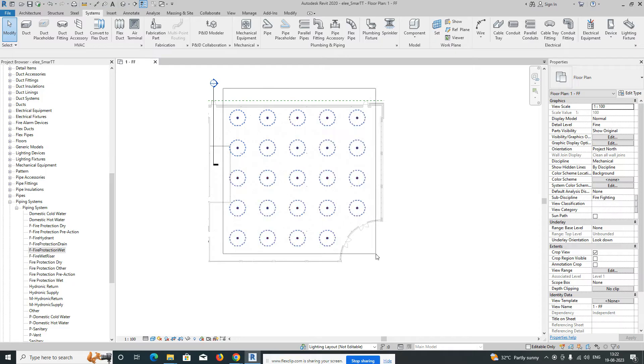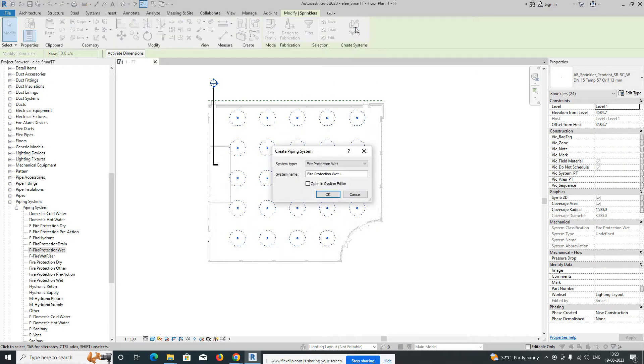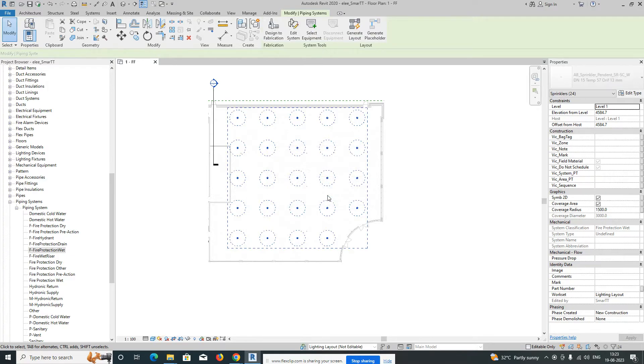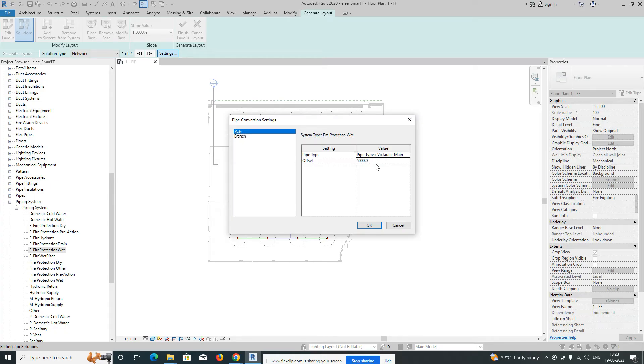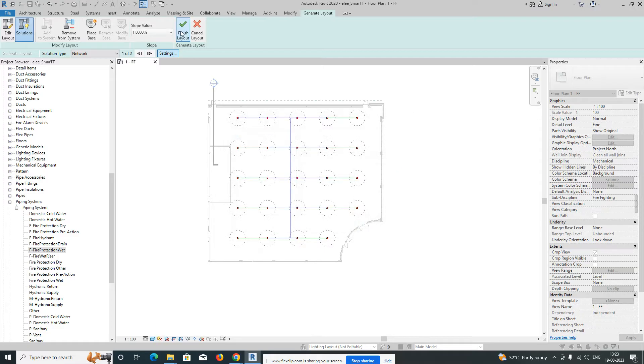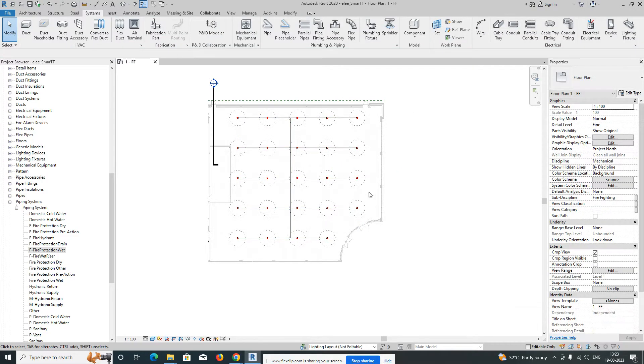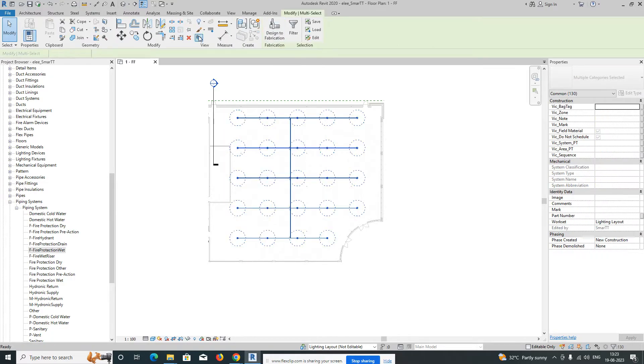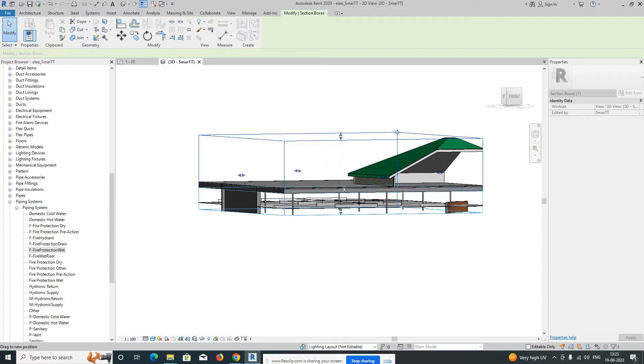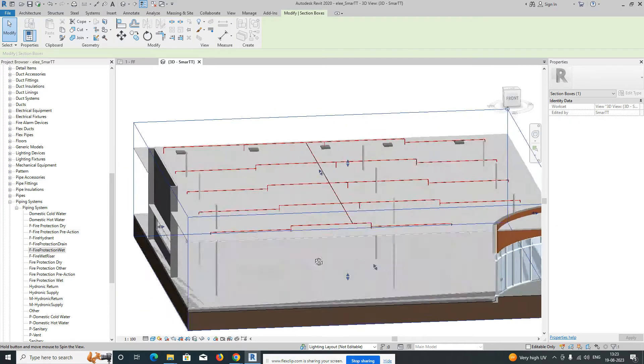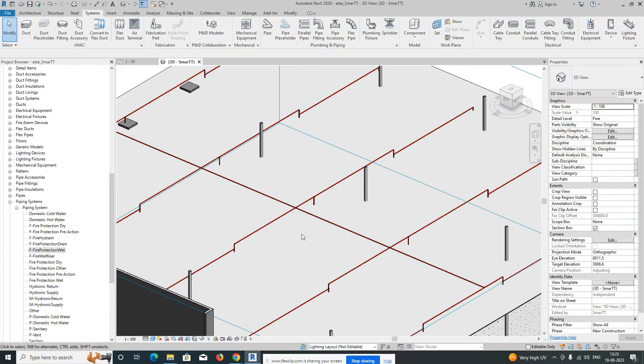I'll show you how to automatically create pipes from the sprinklers. Select all the sprinklers and go to piping — it will show 'Fire Protection Wet'. Click OK, then use 'Generate Layout' — it automatically generates the pipe layout. Go to Settings to define the main branch height offset and branch height. For example, I'm setting the branch offset to 4750mm. Finish, and in the 3D view you can see the connections are automatically created — pipes, sprinklers, main branch, and sub-branches are all connected.